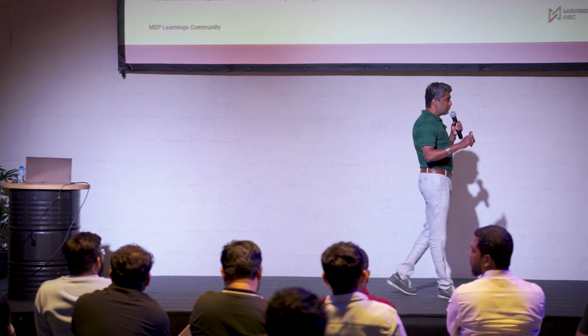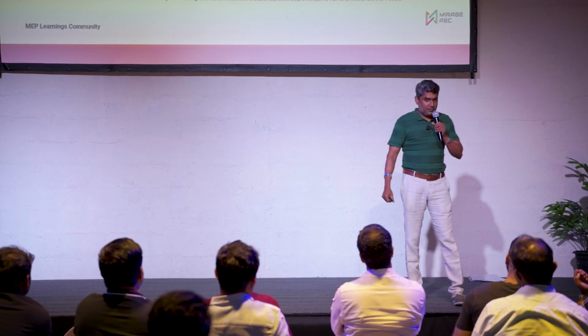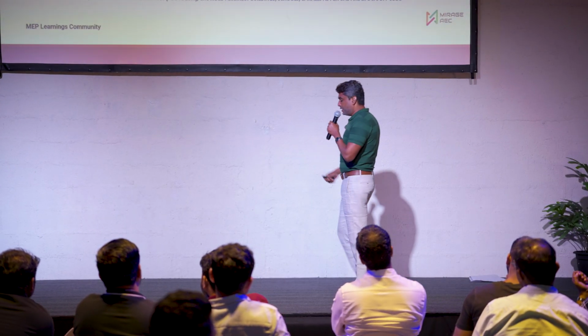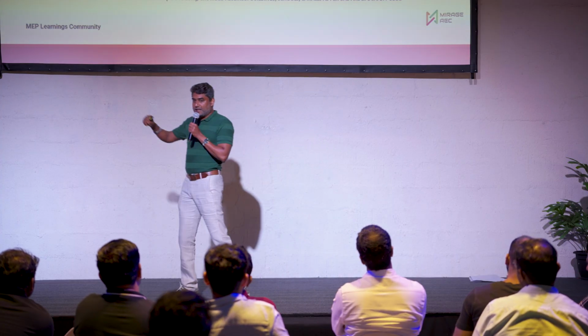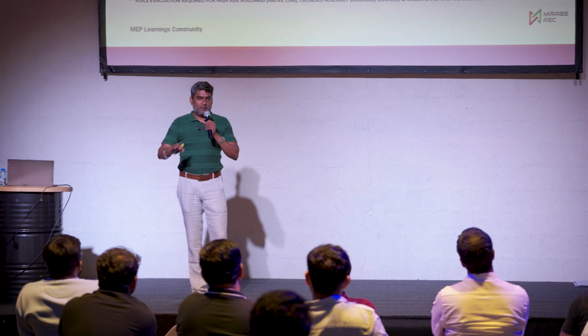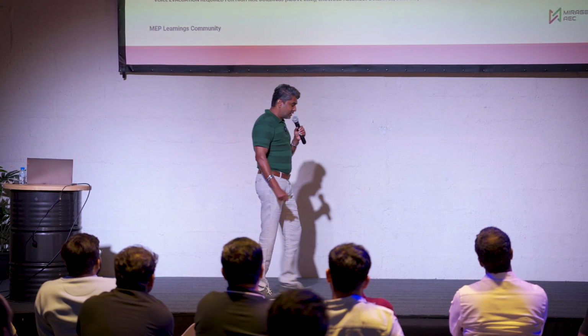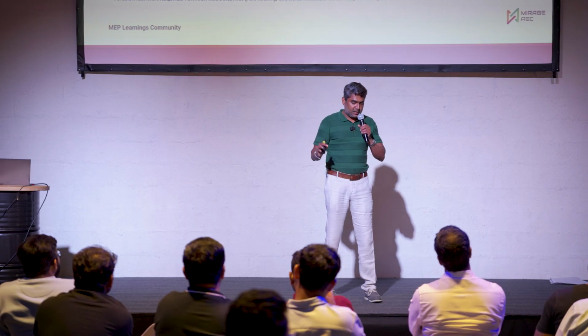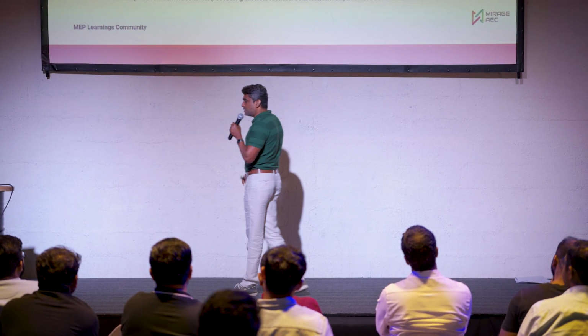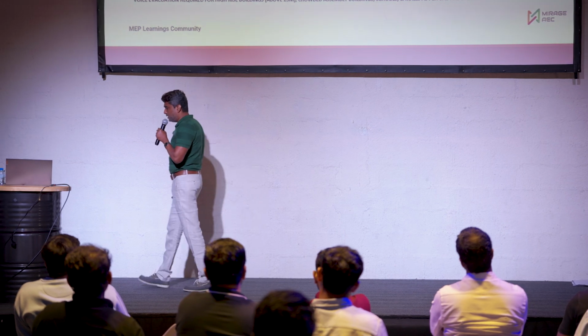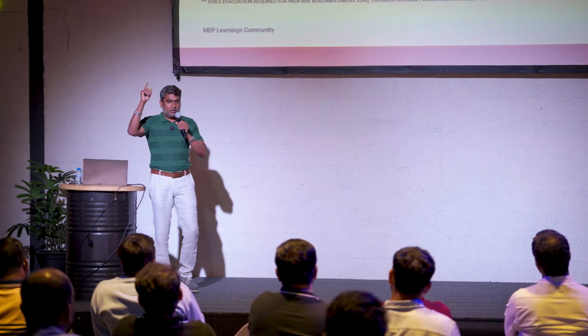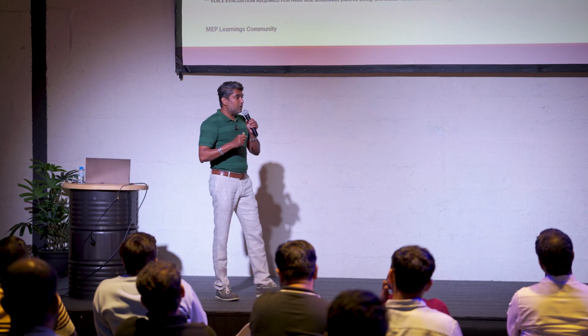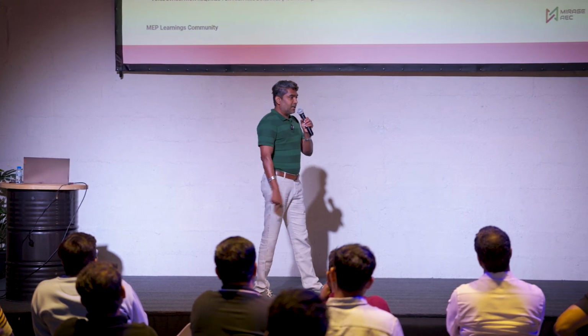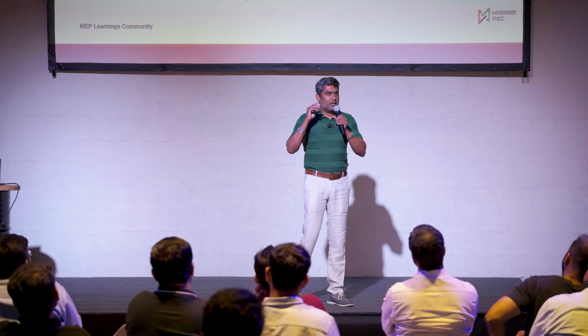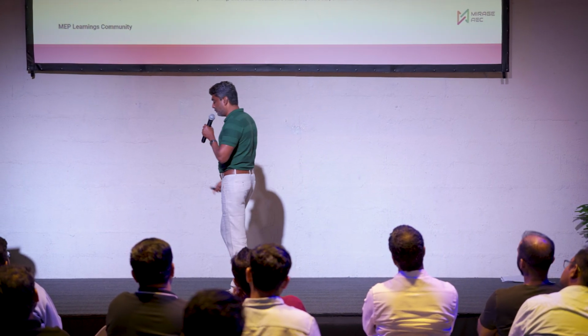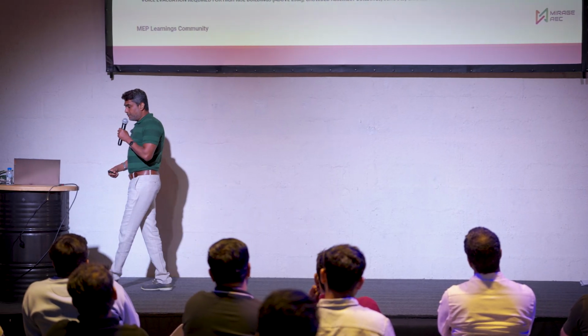The fireman telephone outlets are provided in various areas of the floor just for the firefighters. When they come in, they will grab a handset from the fire command center. The two-way communication system, the firefighters telephone system that we provide in the fire command center, will always have at least 5 to 6 handsets—the project specification will tell you that. They will grab one of the handsets, go around the fire affected floors wherever they want to, and if they want to communicate with the fire command center, they will not use mobile phones or anything. This is the only tool they use to communicate with the fire command center. That's the main purpose of it.